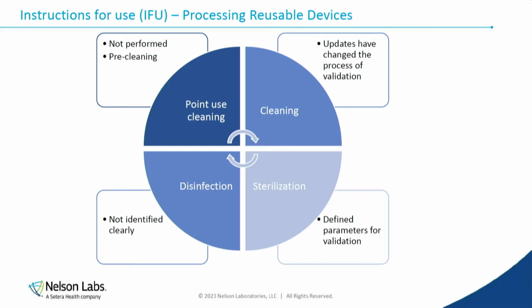Now, point of use cleaning, every manufacturer will have a point of use cleaning. And what happens with point of use cleaning is we omit that from your instructions for use. The reasoning for that is not every facility does point of use cleaning right away, right? You do surgery, you put it in a pan, and then that pan goes somewhere in the basement in a hospital, and they're cleaning it. But are they spraying it with a detergent or a foam that's going to keep it moist? Are things happening? Because of that, we challenge the process that, guess what, they forgot to do pre-processing. And so we're taking it a step further and omitting the step.